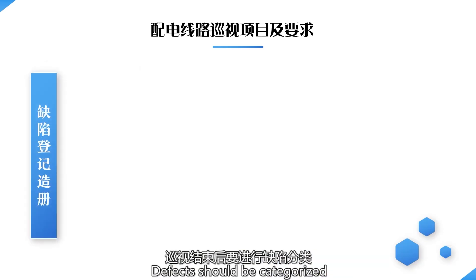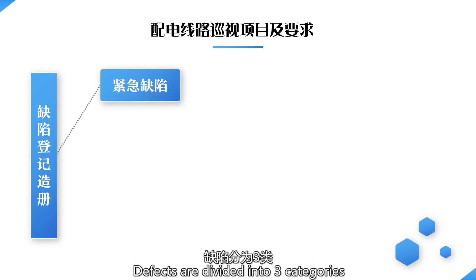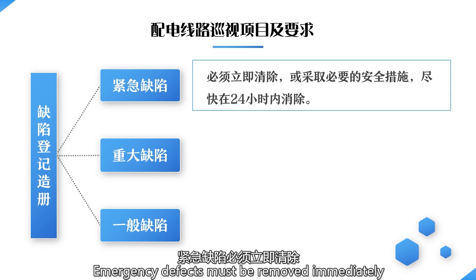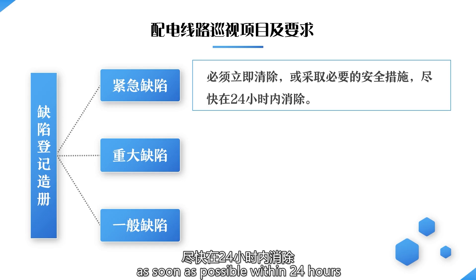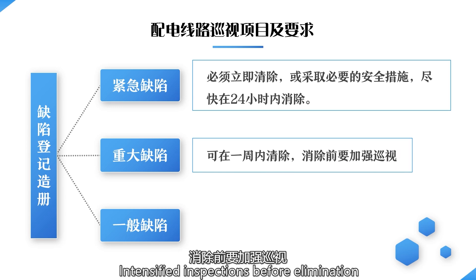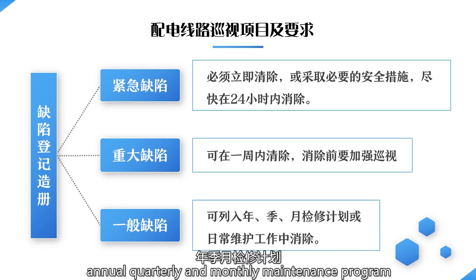At the end of the inspection, defects should be categorized and registered. Defects are divided into three categories: emergency defects, major defects, and general defects. Emergency defects must be removed immediately or have necessary safety measures taken within 24 hours. Major defects can be removed within a week, with intensified inspection before elimination. General defects can be included in annual, quarterly, and monthly maintenance programs or eliminated during routine maintenance.